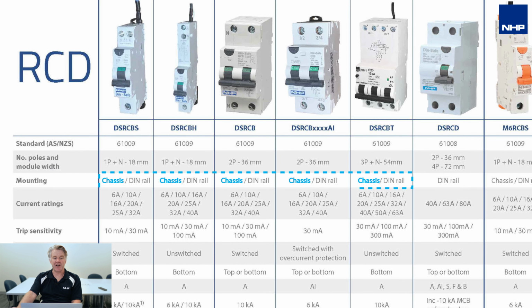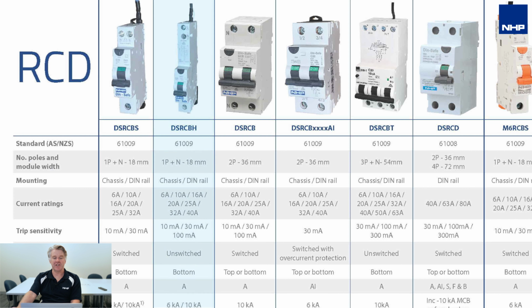Then, is it designed to go on a bus bar chassis, as in the panel board, as you can see here for chassis along here on the third line, or is it just for a DIN rail application where they're all suitable for DIN rail? So depending on the application, you need to choose the right device. There's no point choosing, say, the DSR-CBH unit if it's going in a load center and there's not physically room for the extra long body, where the unit to the left, the DSR-CB-S, will certainly fit in that application.